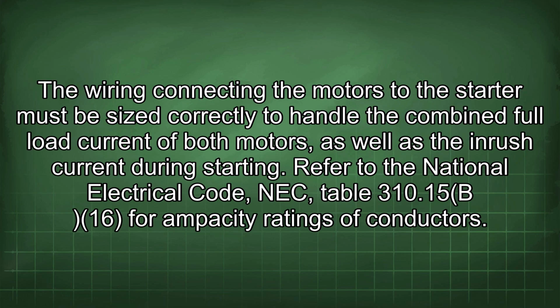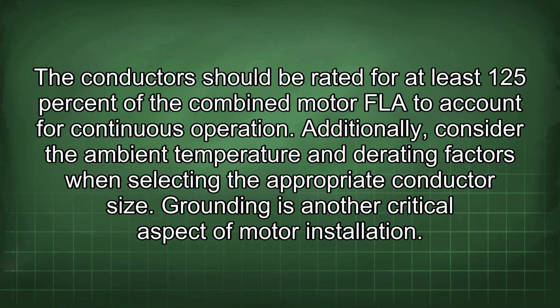The wiring connecting the motors to the starter must be sized correctly to handle the combined full load current of both motors, as well as the inrush current during starting. Refer to the National Electrical Code, NEC, Table 310.15(B)(16) for ampacity ratings of conductors. The conductors should be rated for at least 125% of the combined motor FLA to account for continuous operation. Additionally, consider the ambient temperature and derating factors when selecting the appropriate conductor size.